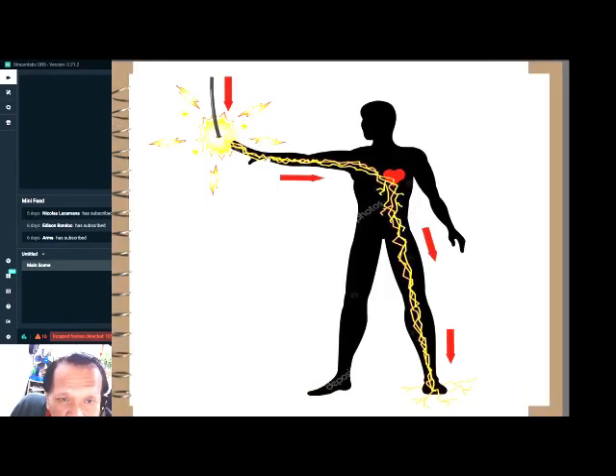So there's something lacking here. I believe there was a lacking ground fault circuit interrupter, or GFCI, also called an earth leakage breaker. The moment there's a ground fault, this device should isolate electricity from non-current carrying parts, like the metal railings or lighting posts. Any metal conductor can become a possible path for electrocution, as we mentioned earlier, where current passes through our body. So something was clearly lacking in that installation in Manila.